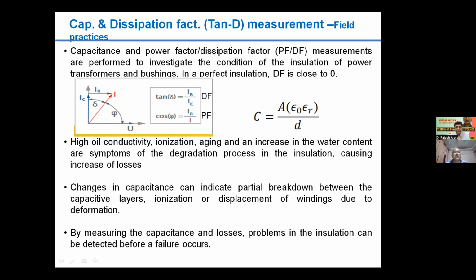In the case of a transformer, these deficiencies may be in the form of contaminations, or in the form of moisture ingress inside the oil and paper. Those kinds of impurities or contaminations may cause loss and may affect the life of the insulation. So during its lifetime, the tan delta measurement is done, and it gives very useful information about the health of the insulation inside the transformer: what is the condition of the oil, and what corrective action is required, whether we service or regenerate the oil, or do some induction heating on the transformer to improve its health. This information may be arrived at by doing this test.